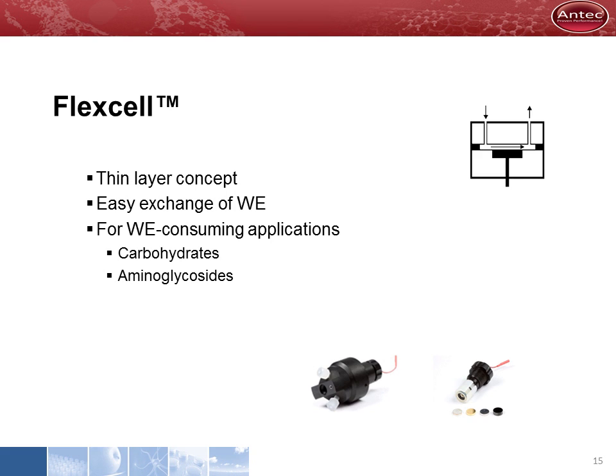The Flexcell is a thin layer flow cell. It can be easily opened and the electrodes are exchangeable. This is a huge benefit for applications where the electrode material is consumed in the detection process, such as the gold electrodes in carbohydrate analysis.